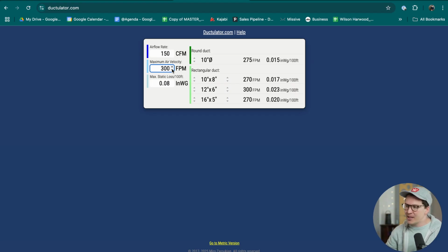And what we care about is both, but we really care about it for the sound of the air. We don't want it to move so fast that we end up hearing the sound coming into our studio. That is a no-no, and that's why we can't have a high rate like 750 or something, where you would get all of these things in here and it would just be a huge mess. So we can't do that. We're going to keep this down to 300 feet per minute or less, like I said.